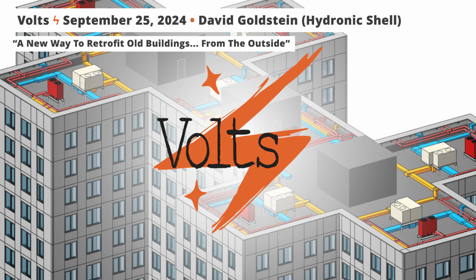But with an office building, you can have tons of computers, commercial density of lighting, and lots of people packed into a space, so your internal gains are still much higher even though you're super insulating the facade, so your loads overall are higher. The other thing is you need a lot more ventilation air for a space like that. If you have 30 people in a section of an office, they need much more ventilation air than just a living room does. So when we're talking about squeezing ducts into a narrow facade cavity, it's a lot harder if you need much higher volumes of ventilation air.